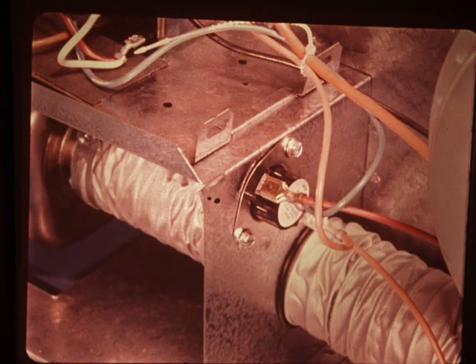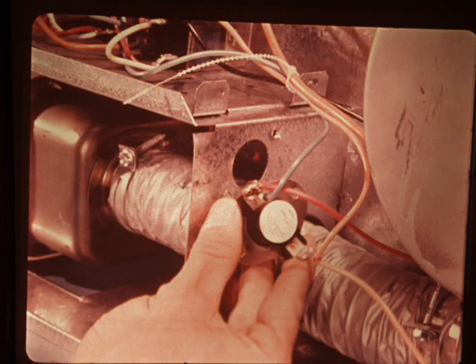The fan switch is on the right side of the warm air housing. Disconnect the electrical leads and take out the 2 mounting screws to remove it. You'll recall this is the switch that allows the blower to keep running for a time after the burner shuts down. Check the condition of the contacts, which should be open at room temperature.